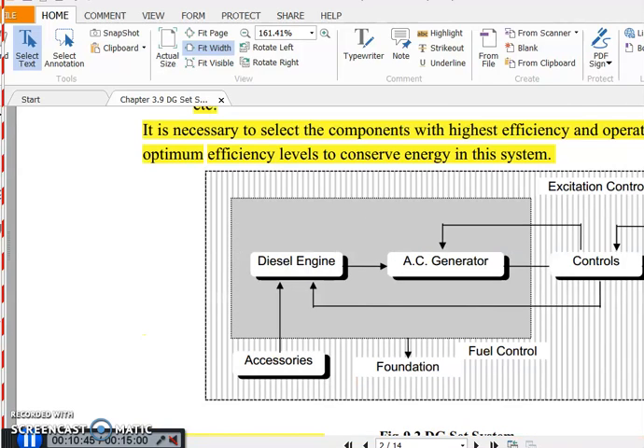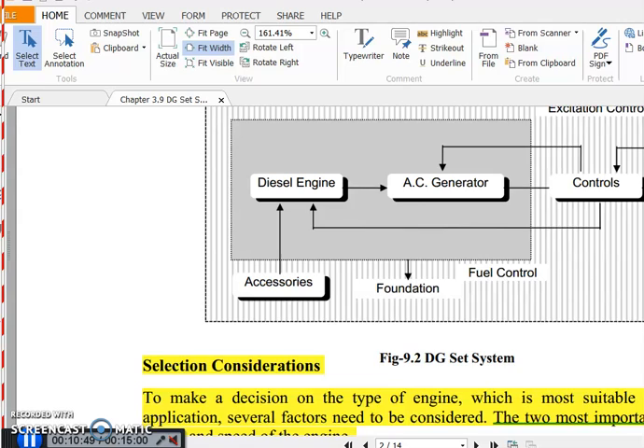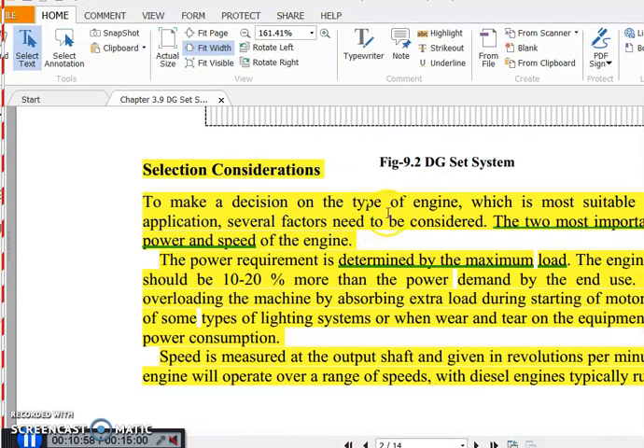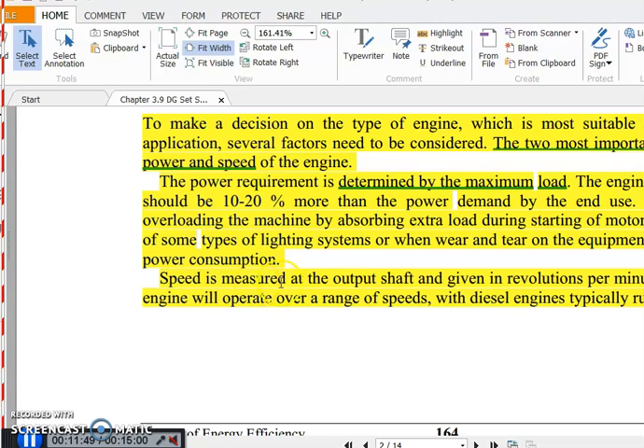The engine power rating should be 10 to 20 percent more than the power demanded by the end user. For example, if you have a 100 kVA load, you need at least a 120 kVA capacity diesel engine. This provides a backup to handle machine overloading — such as the extra current consumed during motor starting, which causes flickering in tube lights.